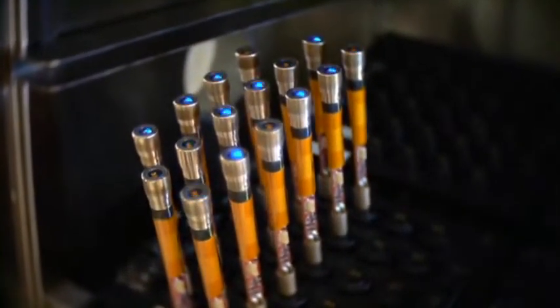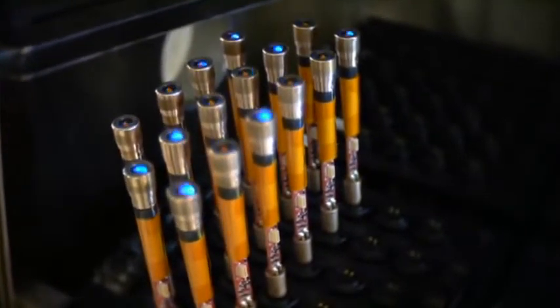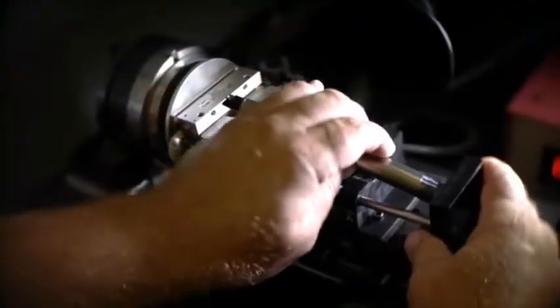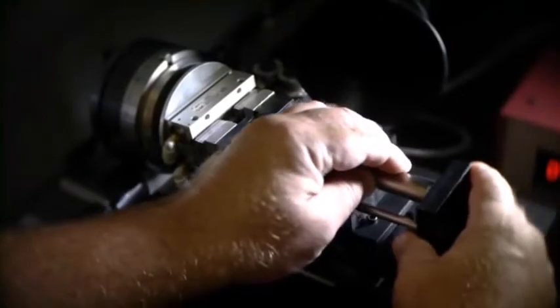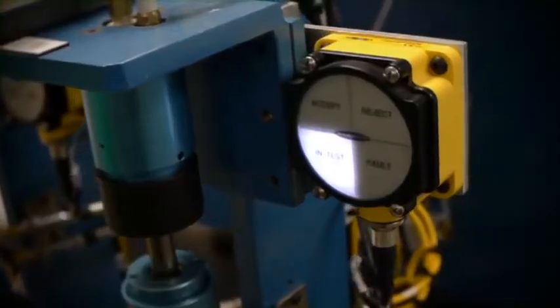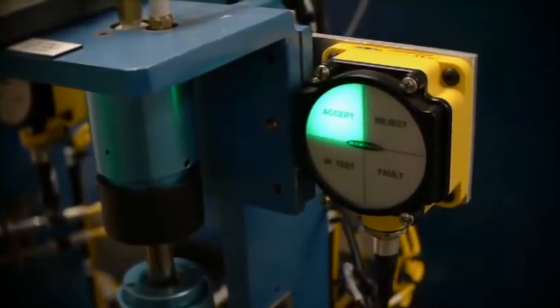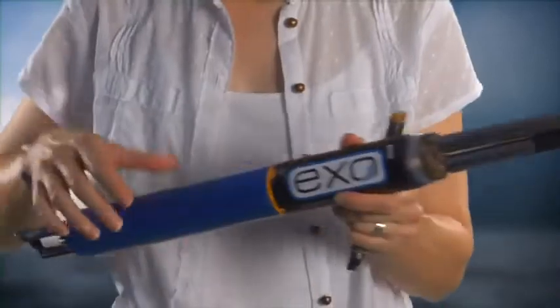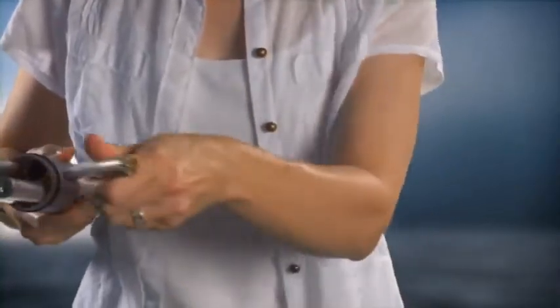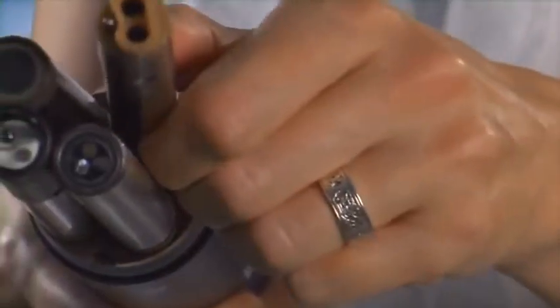Its smarts also allow the sonde to automatically recognize the sensors. Sensors are made of strong and corrosion-free titanium that are welded shut and pressure tested to a bulletproof leak-tight design. In addition to these features, the sensors and the sensor ports are universal, meaning any sensor can conveniently be plugged into any port on the EXO sonde.